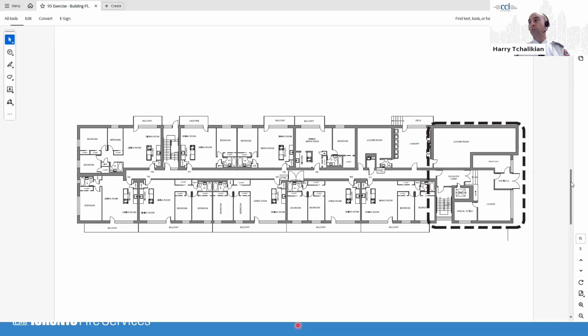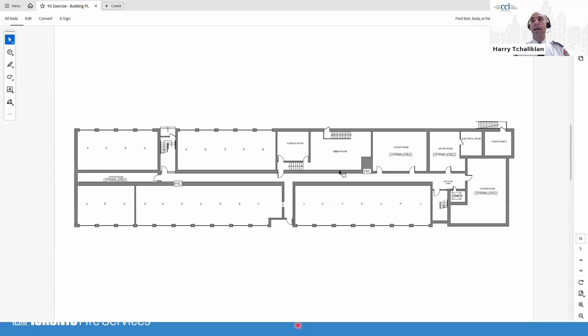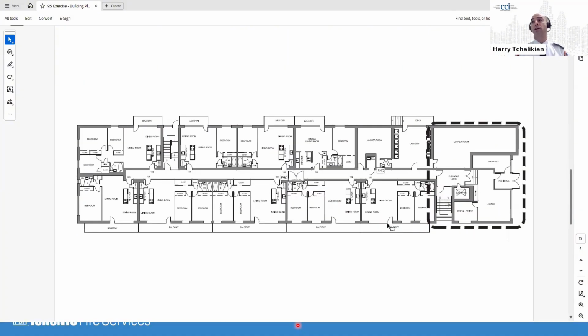So do we have a storage garage? Let's go back up to the ground floor, sorry, the basement floor. And what you see here where my cursor is, these are all parking spaces indoors. So this meets the definition of a storage garage. People will be parking their cars there. So by virtue of that, in combination with the fact that we have a furnace and boiler, now all of a sudden, the entire ground floor, all these dwelling units need carbon monoxide alarms. They needed these carbon monoxide alarms already as per the 2015 fire code. So let's see what's new.